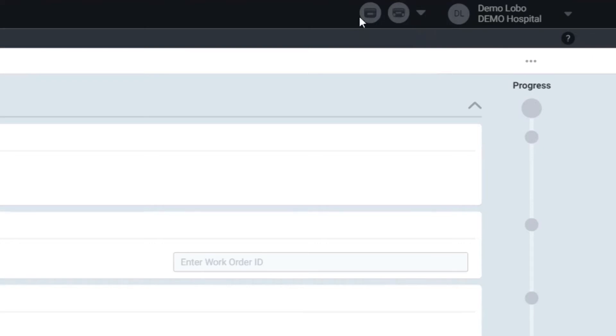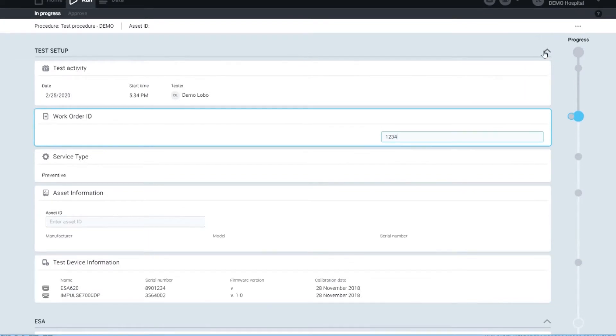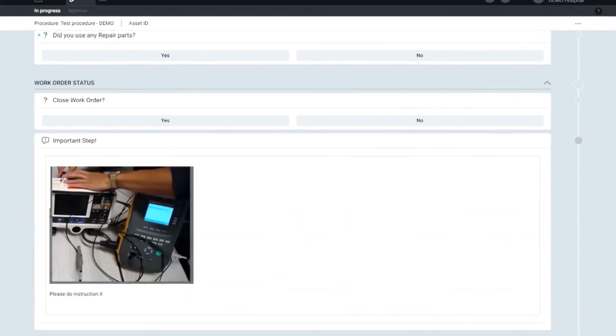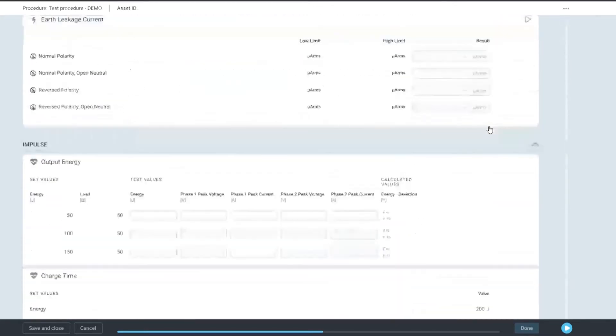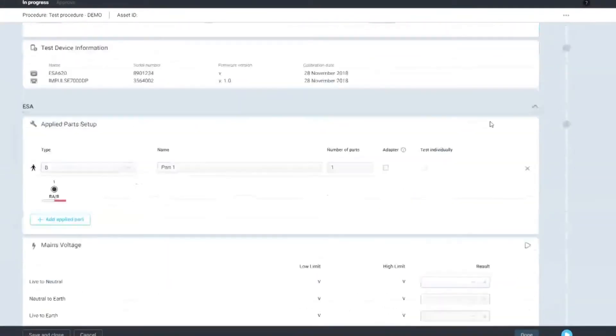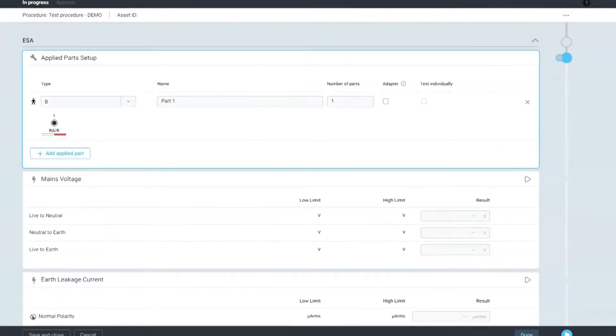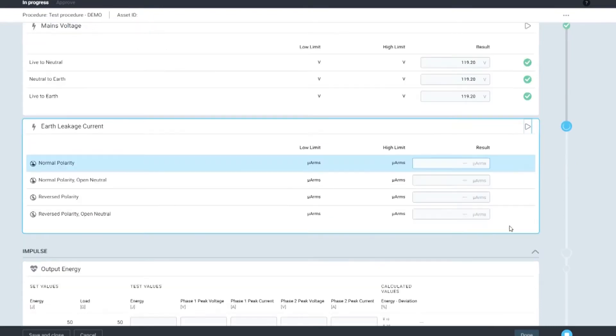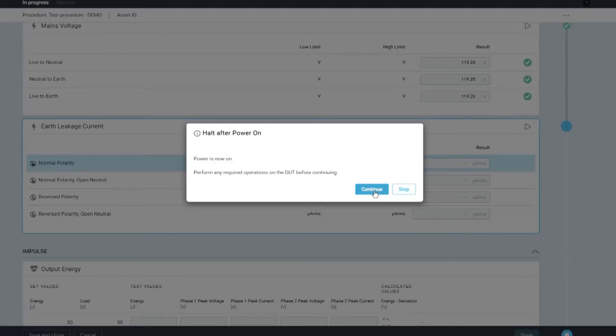All you have to do is click 'Run Procedure.' I have already attached my two Fluke equipment that are necessary for the demo. Now I add the work order that I want the reports to be uploaded to in my asset management software and press play. I'll select the part that I want to start from and press play. As you can see, the data is going to be collected and auto-populated here, and if it covers the limits — the low and high — it will have a check.